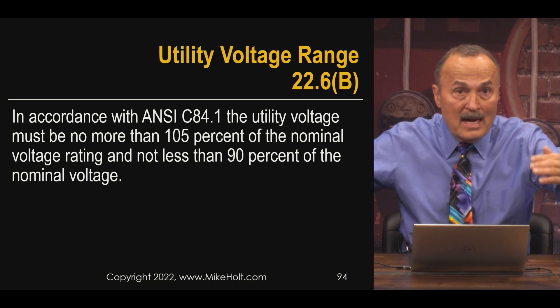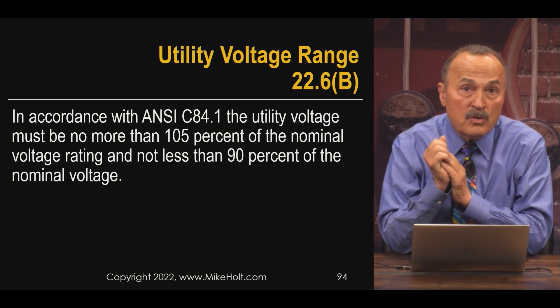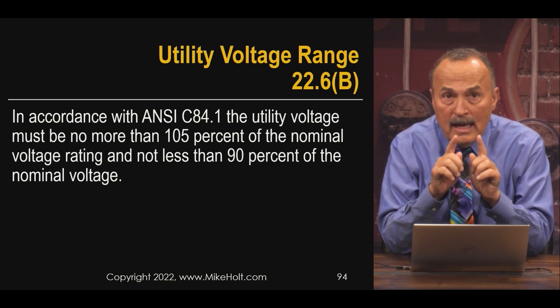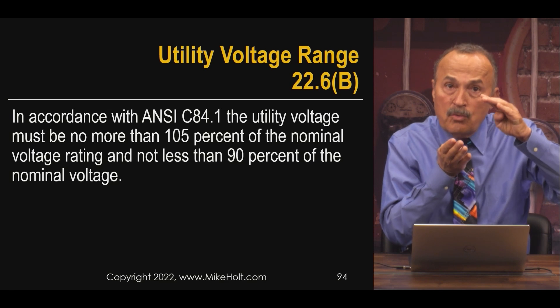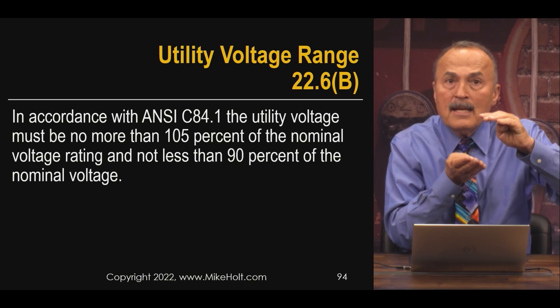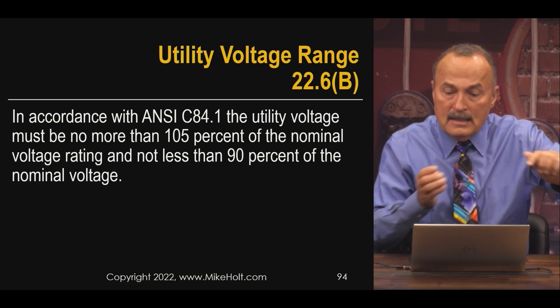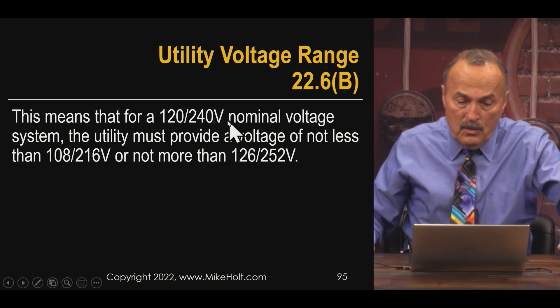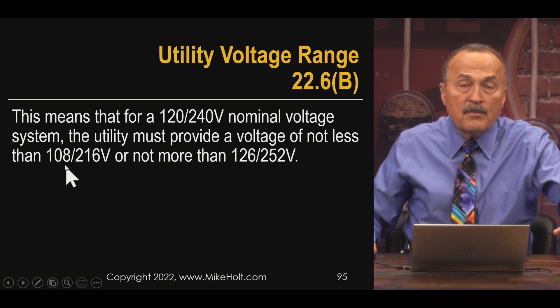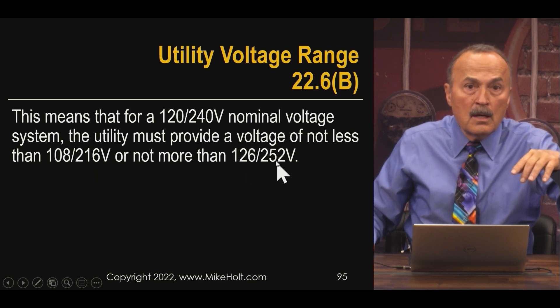No more than 5% above the nominal system voltage. In other words, they have to give you no more than 5% more than 120 volts. And also, they have to give the customer no less than 90% of the nominal system voltage. The utility is required to deliver something the customer can depend on — not more than 105% and not less than 90% of nominal. So on a 120/240 volt system, that's not less than 108/216 volts, and not more than 126/252 volts.